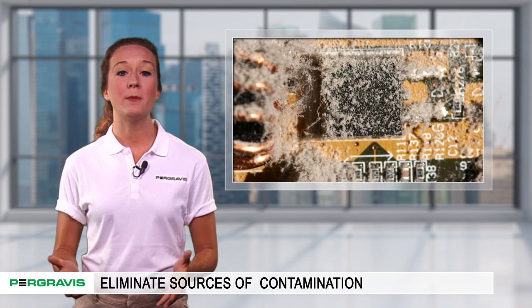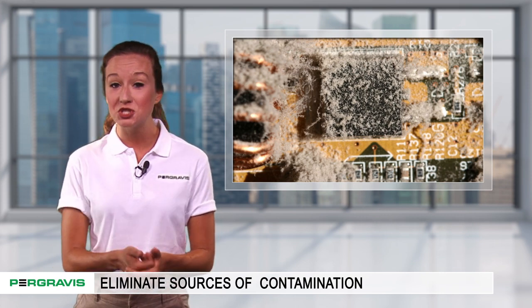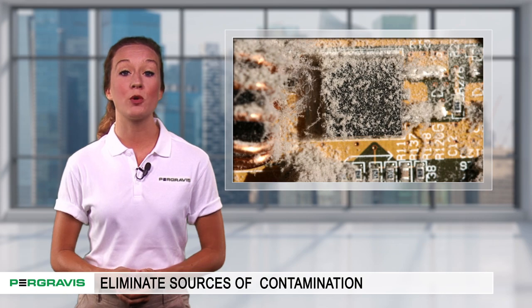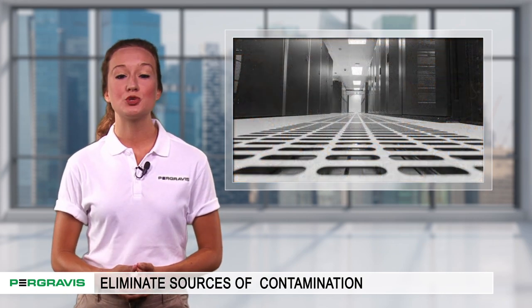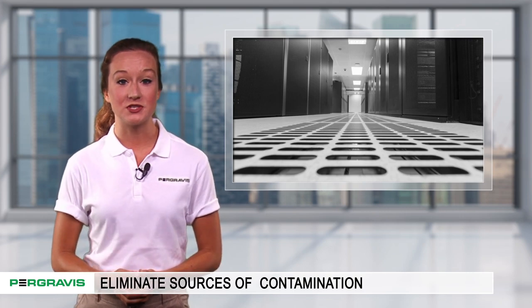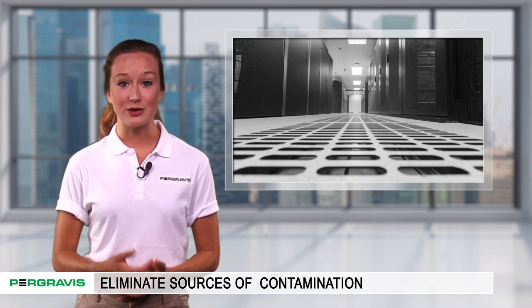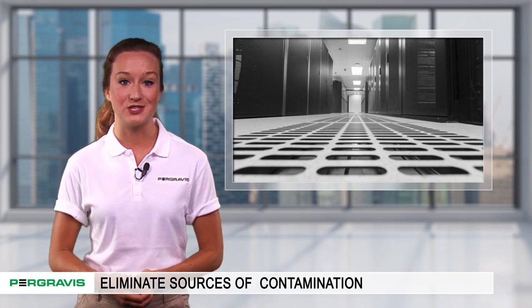For instance, common acoustic ceiling tiles are comprised of cellulose fibers, and they shed over time. Likewise, cardboard boxes shed large amounts of cellulose fibers too. These fibers are transported by air currents to heat sinks, fan blades, and air filters. The accumulation of fibers can coat fans and clog heat sinks and filters, reducing cooling efficiency.